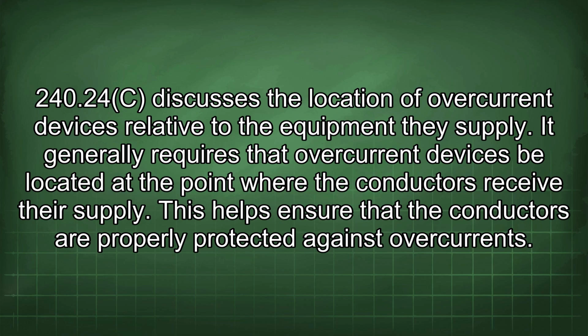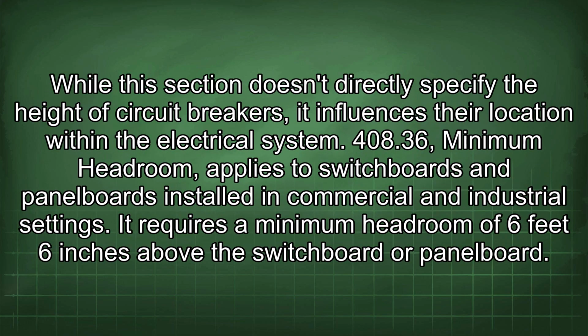240.24(C) discusses the location of overcurrent devices relative to the equipment they supply. It generally requires that overcurrent devices be located at the point where the conductors receive their supply. This helps ensure that the conductors are properly protected against overcurrents. While this section doesn't directly specify the height of circuit breakers, it influences their location within the electrical system.